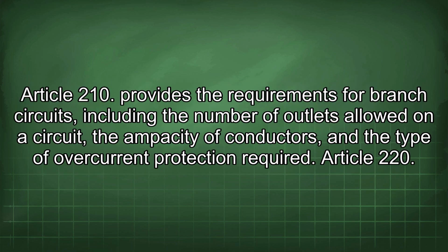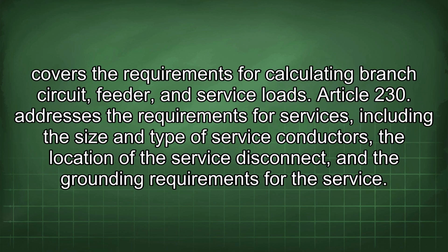Article 210 provides the requirements for branch circuits, including the number of outlets allowed on a circuit, the ampacity of conductors, and the type of overcurrent protection required. Article 220 covers the requirements for calculating branch circuit, feeder, and service loads. Article 230 addresses the requirements for services, including the size and type of service conductors, the location of the service disconnect, and the grounding requirements for the service.